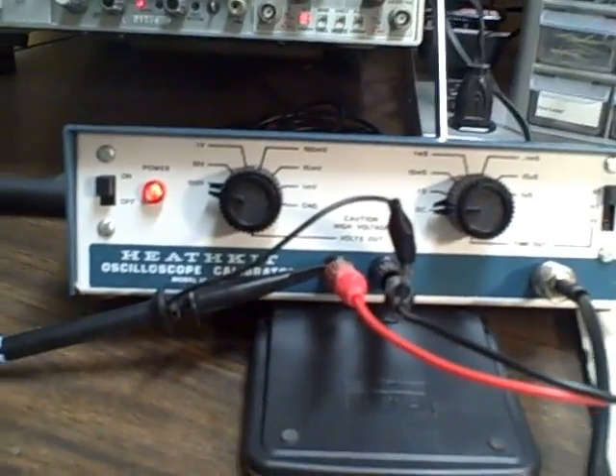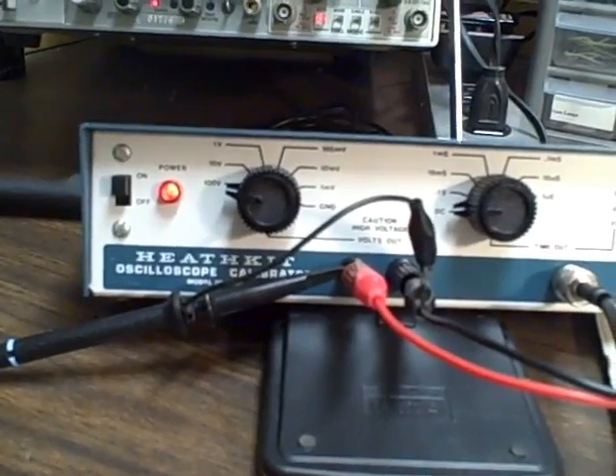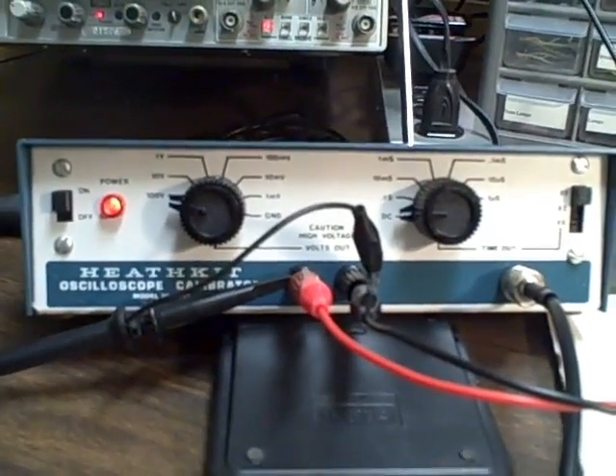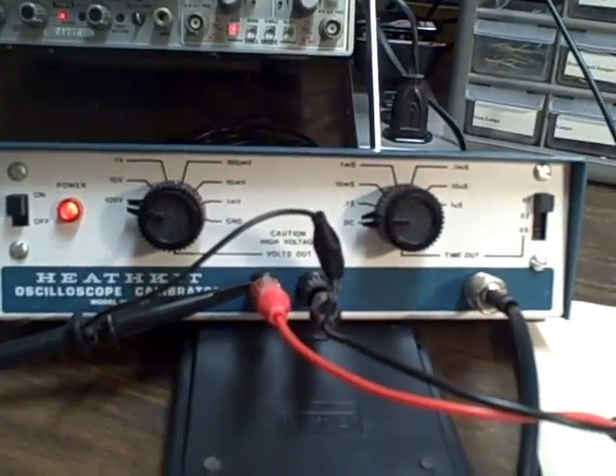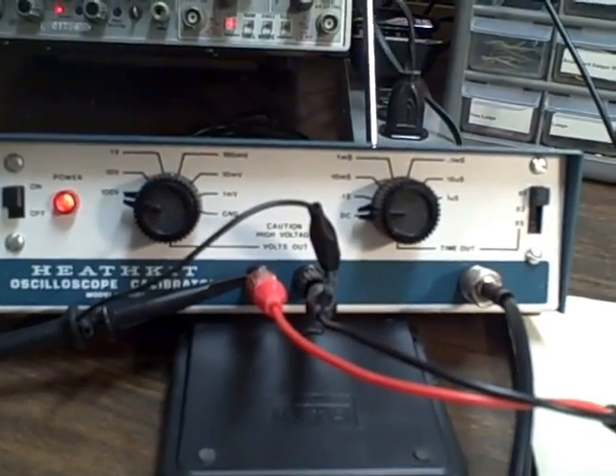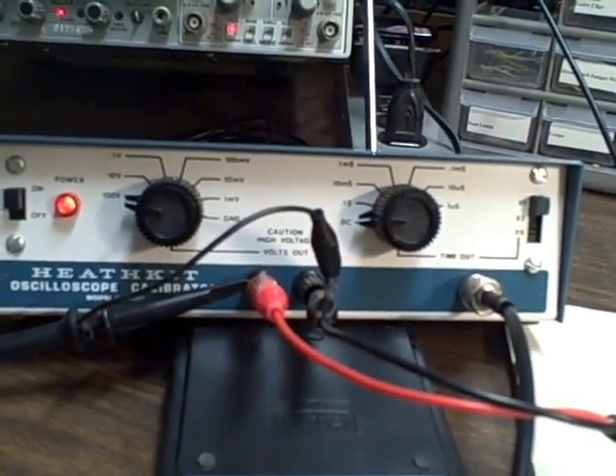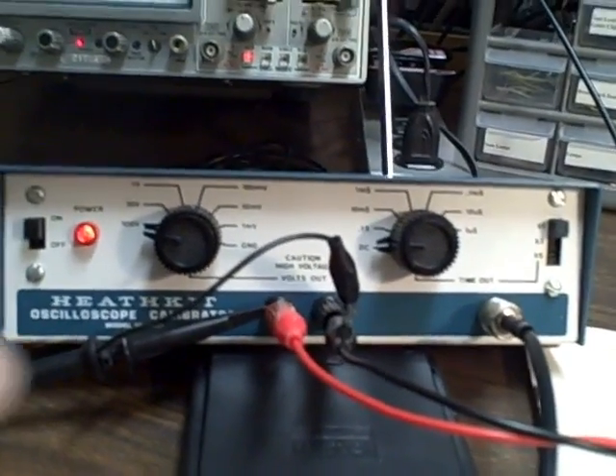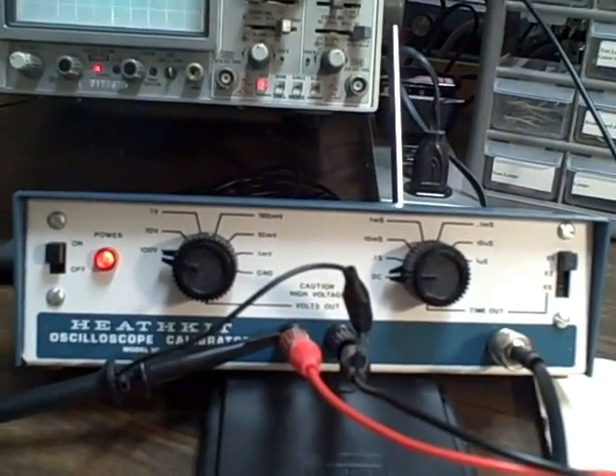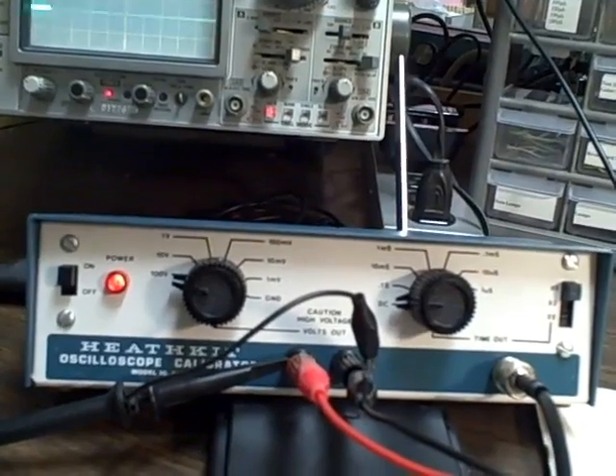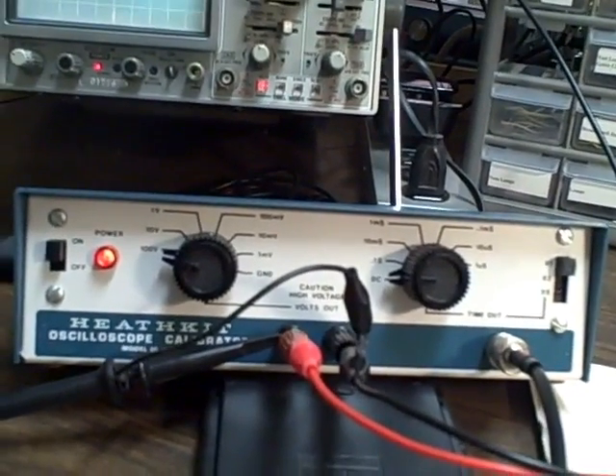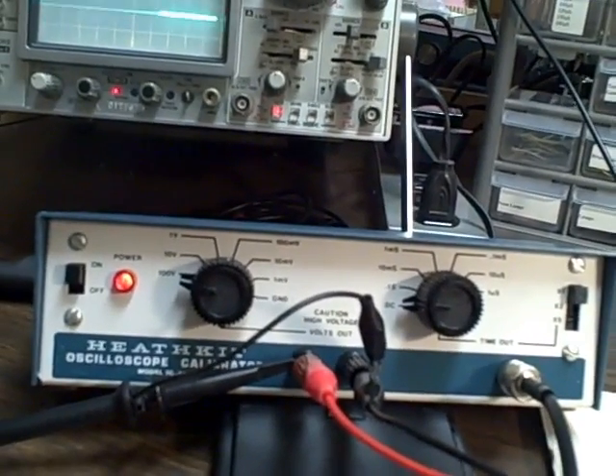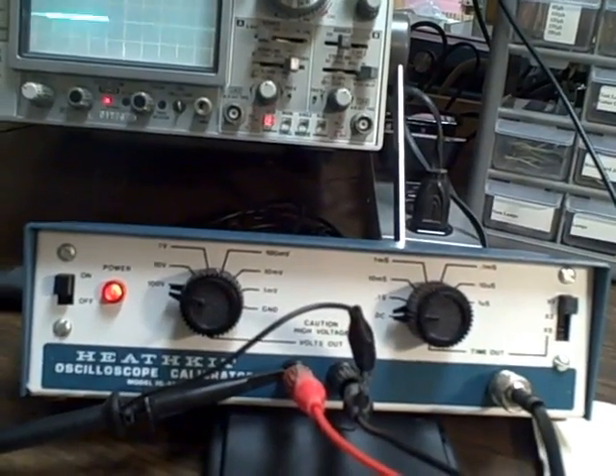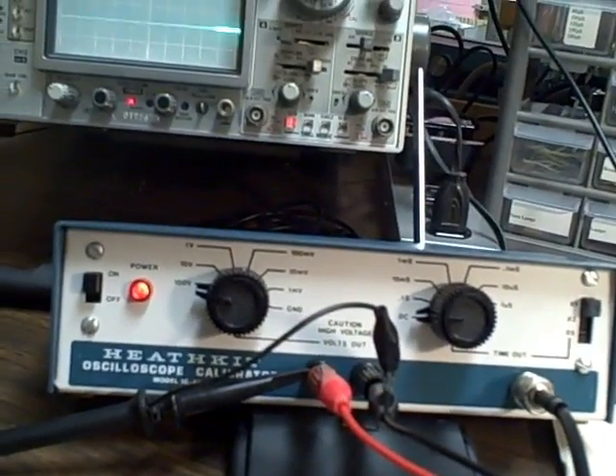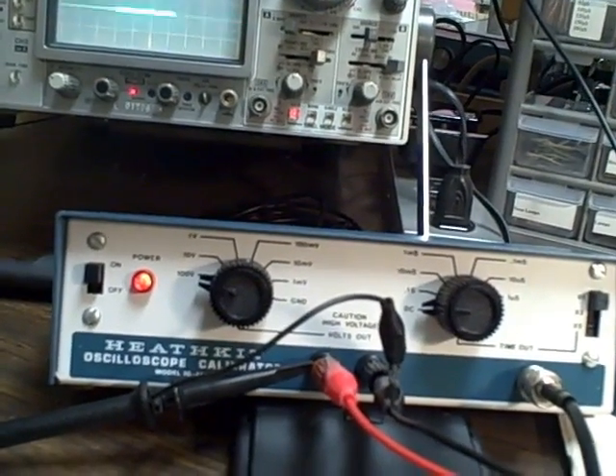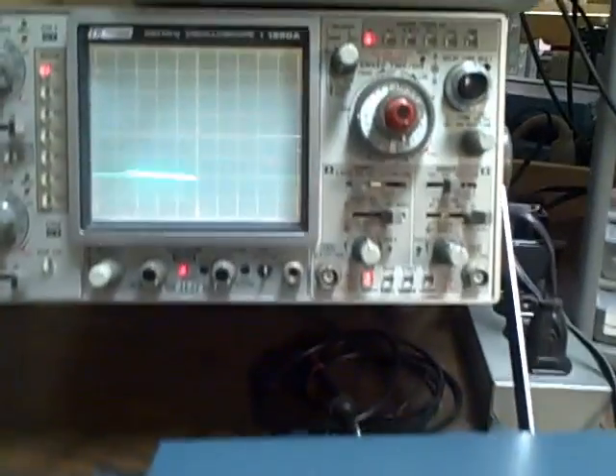So you'll be able to adjust your vertical amplitude, the gain settings in your scope. When you get to the part of a manual that says please adjust trim pot number A1R2 to provide 5 divisions at 10 millivolts per division, or whatever it tells you to do, you can do that. You can set up your 10 millivolts, well, it'd be 50 millivolts over a 5 division 10 millivolt range, and then you can adjust to it. And if it tells you that you need to adjust your time base for a 10 microsecond pulse, and you want to adjust so that it shows up on the graticule at every step, you can do that as well.